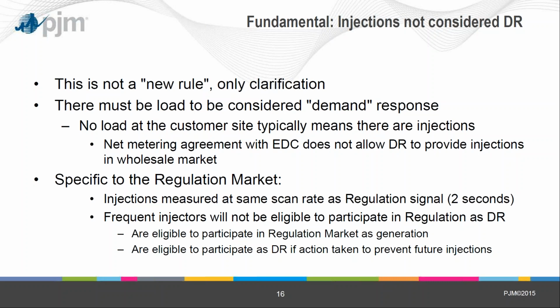So what that means is if you're siting a battery at a facility, you either need to do two things. You need to ensure that the load is larger than the battery resource in such a way that the battery will never be injecting beyond the meter when it's providing a service. Or if there are going to be injections at that facility because maybe there's on-site solar power or other generation, you need to only provide the demand response service during hours in which there won't be injections on the system. So to give you an example of that, if I'm siting a battery and a solar facility behind the meter and I want the battery to participate as a demand response resource, I would only use that battery to participate in the market during hours in which the solar power will not be injecting through the system.